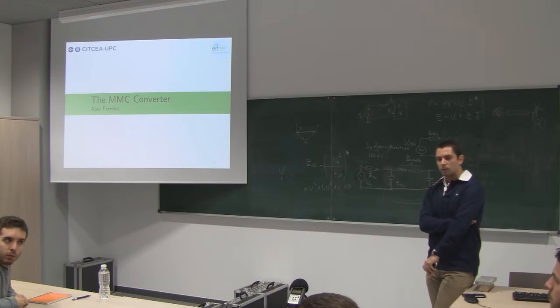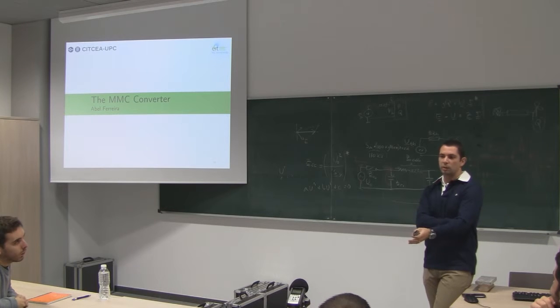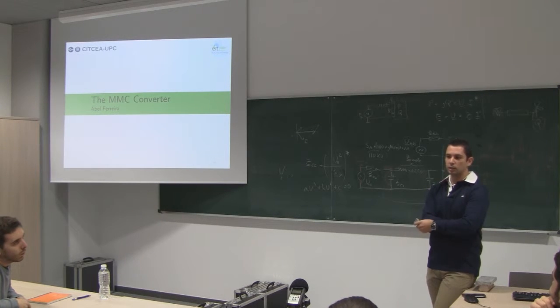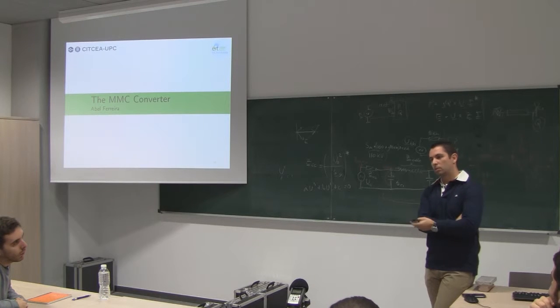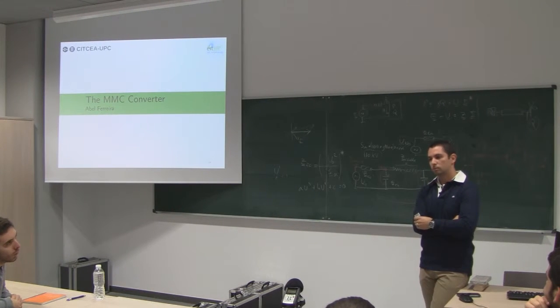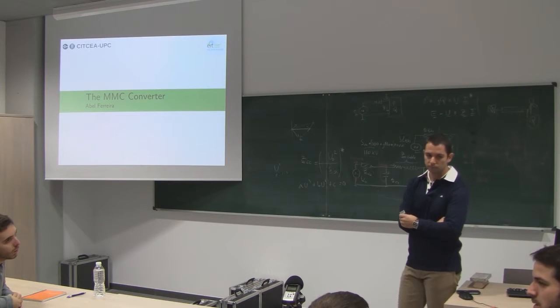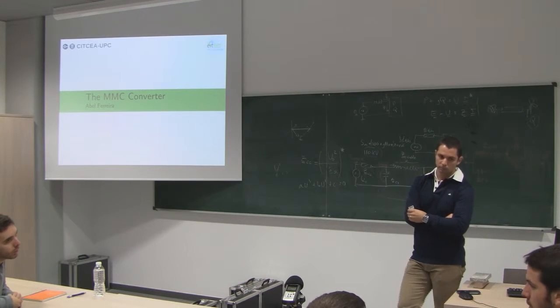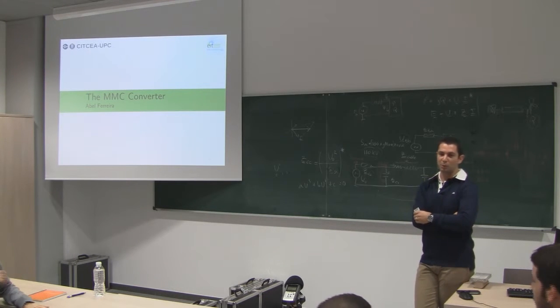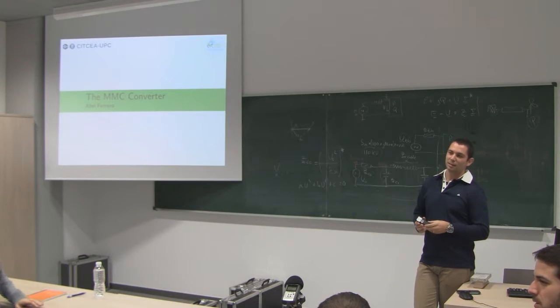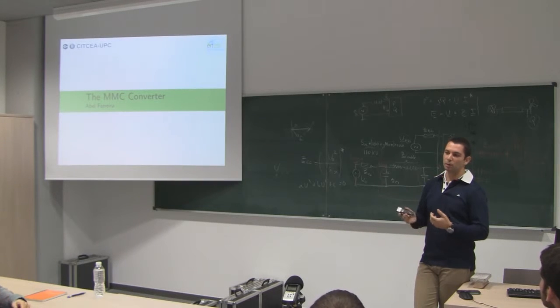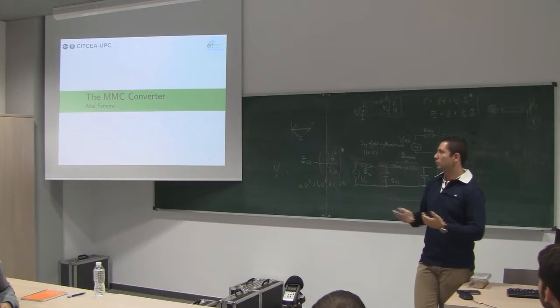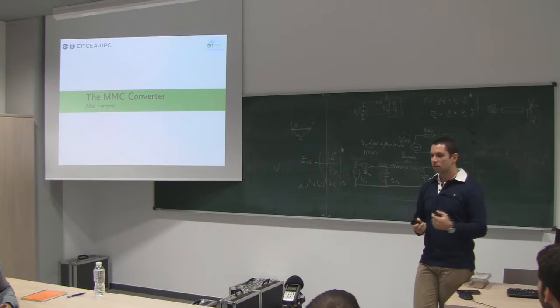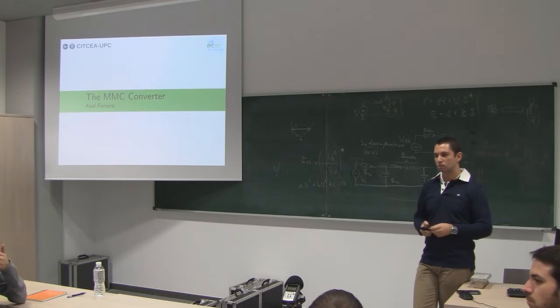It's also because if a fault happens on the DC side, the cables can collapse if you increase the voltage too much. I don't know if they have problems with partial discharges or other issues, but we are not the cable guys—we are focused mainly on converters, so I cannot really tell you why. But the thing is, if you want to transmit more power, you increase the voltage. With these MMC converters you just put more modules, let's say, but you can't do that because of the cable. So the cable nowadays is what's limiting the power issue.